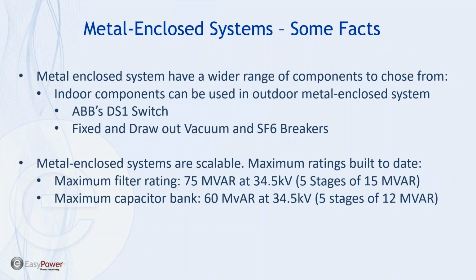In addition to being able to use the same components, a metal-enclosed system also has access to other types of devices. The ABB DS1, for example, is a 600 amp transient free switch. That's an indoor only rated switch. We also have access to fixed and draw-out vacuum circuit breakers and SF6 breakers. These are all indoor rated devices. So there's a much bigger choice of components for the metal-enclosed solution. Metal closed solutions are scalable, and it's much like an open air solution.